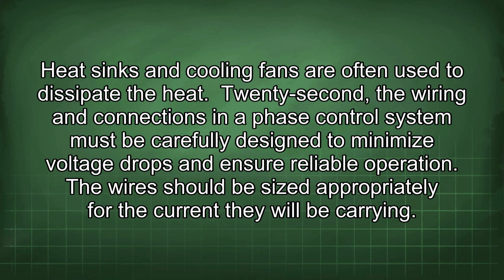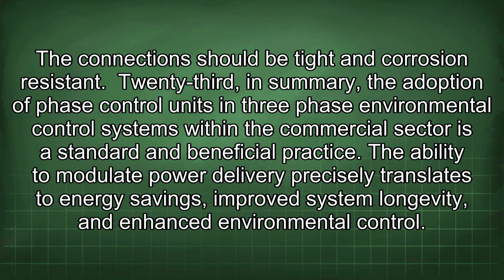22nd, the wiring and connections in a phase control system must be carefully designed to minimize voltage drops and ensure reliable operation. The wires should be sized appropriately for the current they will be carrying. The connections should be tight and corrosion resistant.